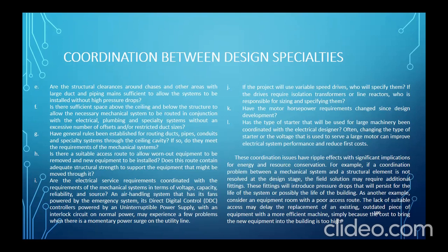Often changing the type of starter or the voltage that is used to serve a large motor can improve electrical system performance and reduce first cost. So these coordination issues have a ripple effect with significant implications for energy and resource conservation. For example, if a coordination problem between a mechanical system and a structural element is not resolved at design stage, the field solution may require additional fitting.